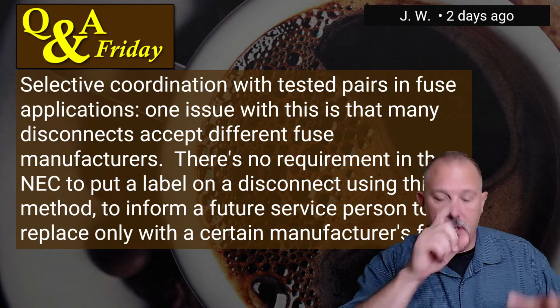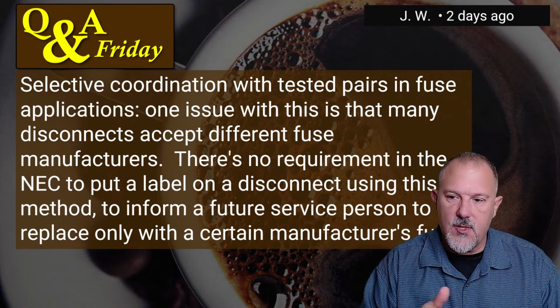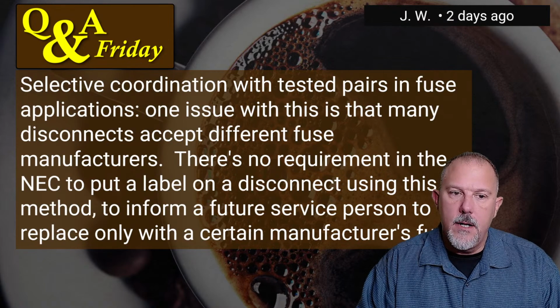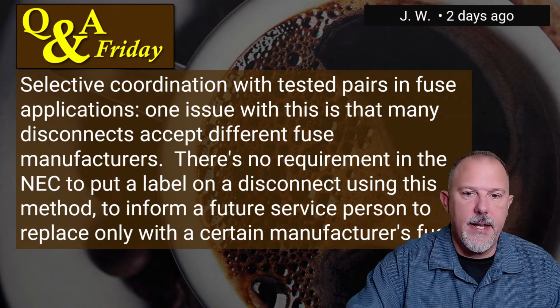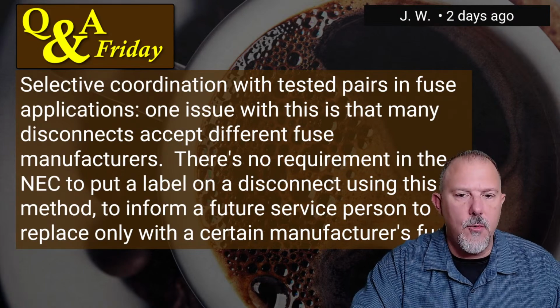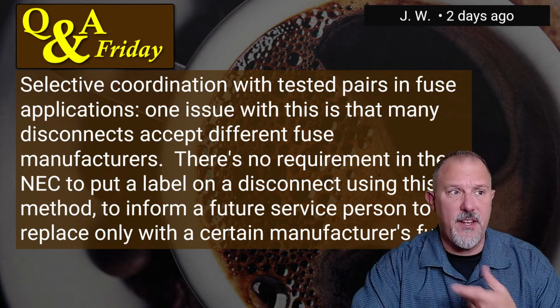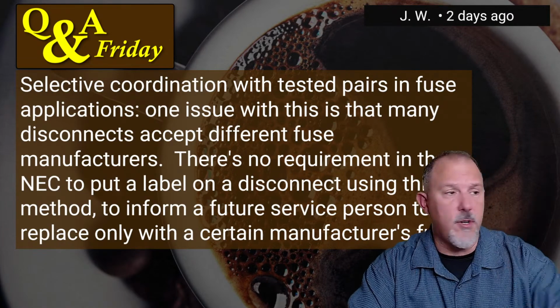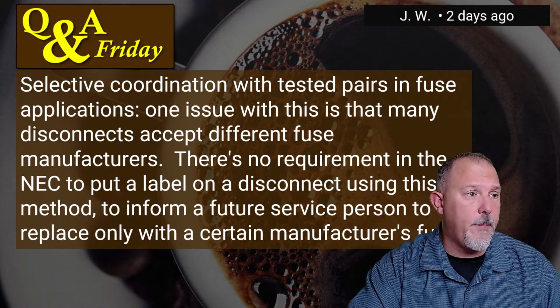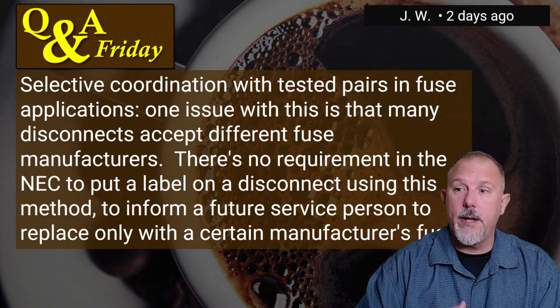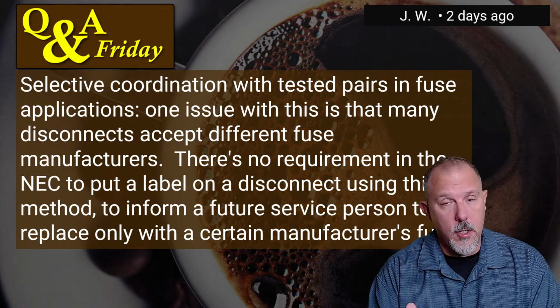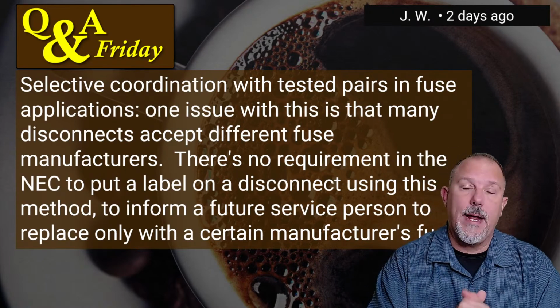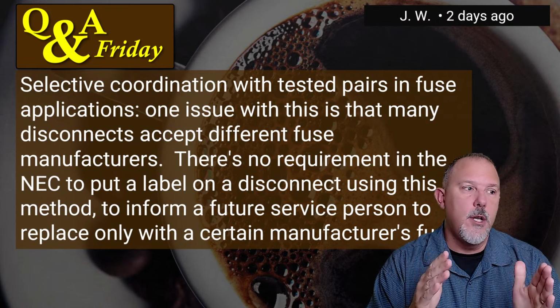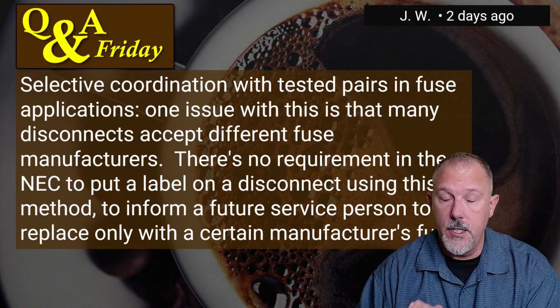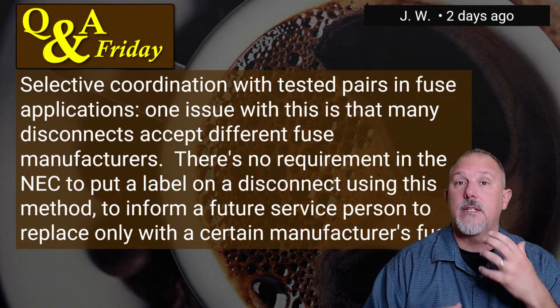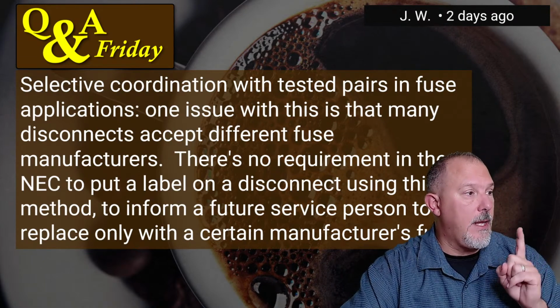So JW, there are no requirements right now that say to inform future service to replace only with a certain manufacturer. And I would say it's not just the manufacturer, it's also the manufacturer and model number. What's good for the goose is good for the gander. That's not just a fuse thing. Circuit breakers as well, either replacing circuit breakers or if you are looking at the settings. Any of the settings on a circuit breaker are very critically important to make sure that you maintain the selectivity.